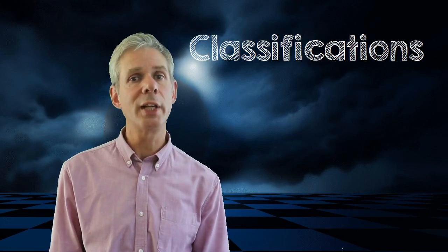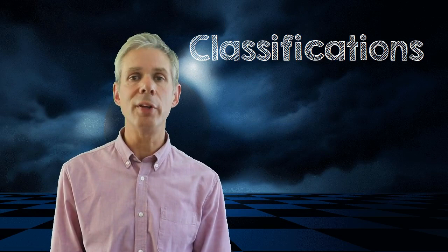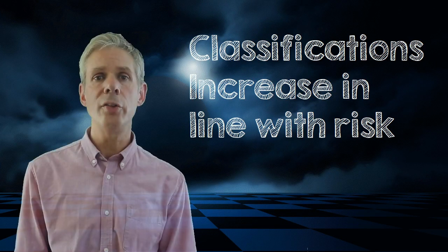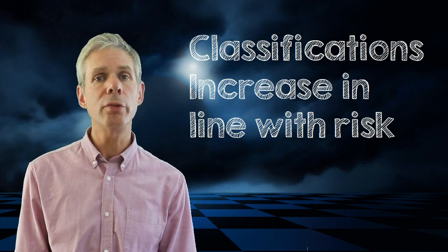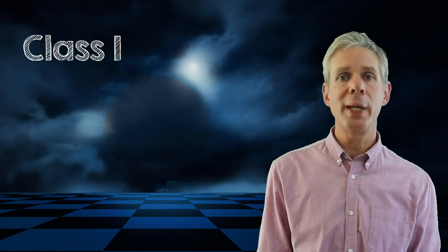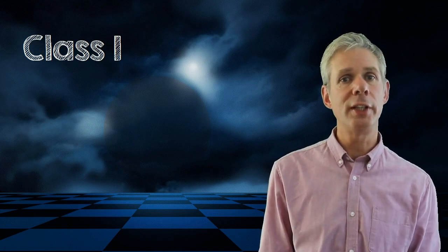First off, you should be aware that medical devices are grouped into classifications according to the risk they present to the user and patient. There's a process you follow to find out which class your medical device fits into. It's described in lots of detail in Annex 8 to the MDR. Classes increase in risk from the lowest Class 1 through to Class 3. So we have the simplest, least risky devices sitting in this Class 1. Basically, these are non-invasive devices that don't store or channel body parts or fluids.